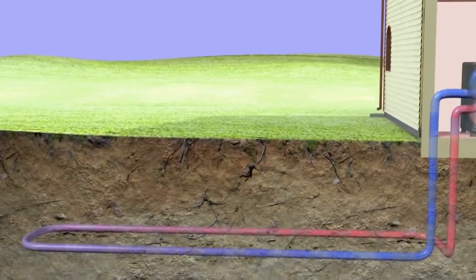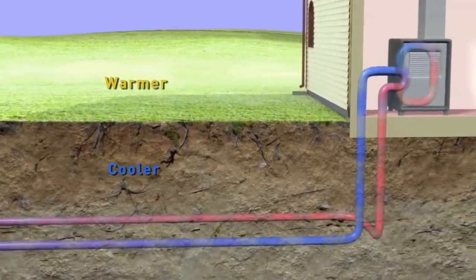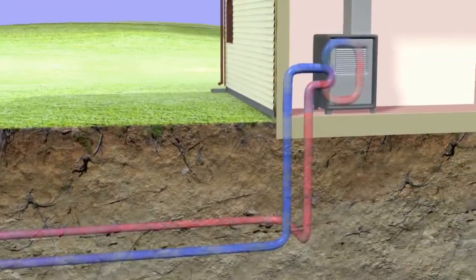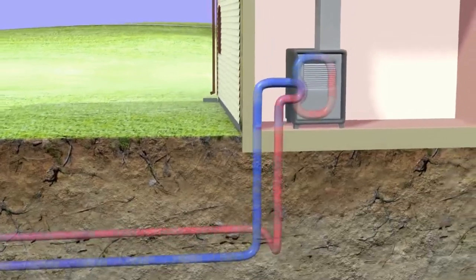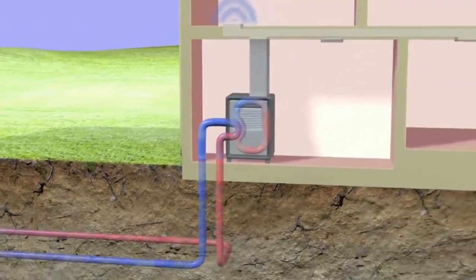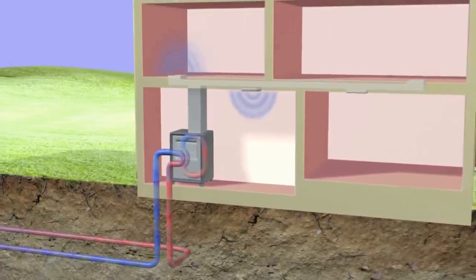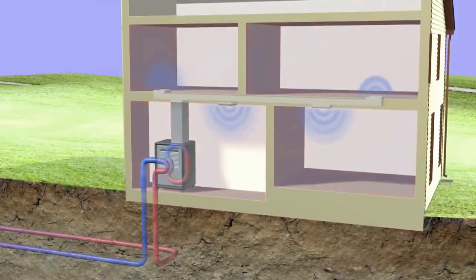In the summertime, the system works in reverse. When it's hot outside, the temperature below the surface is cooler than the summer heat, so the fluid in the loop absorbs heat from the building and sends it underground. The ground's lower temperature cools it, and it's circulated again and again, saving you money on air conditioning.